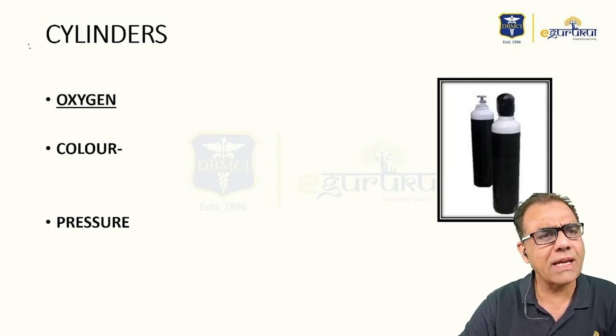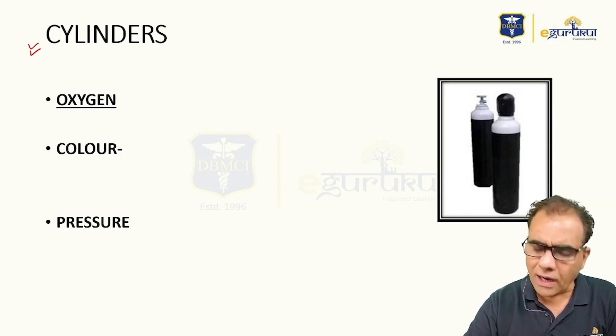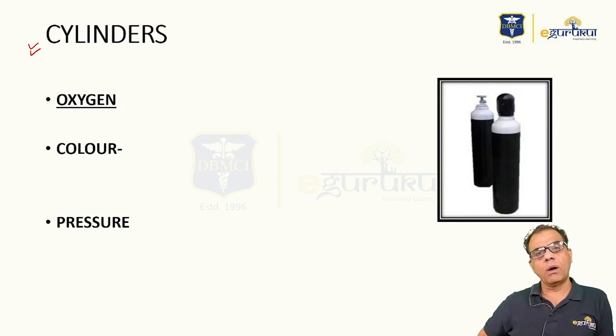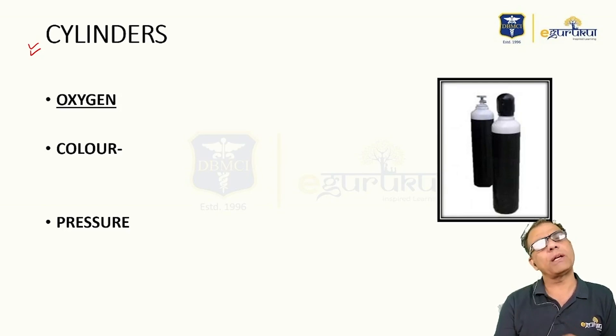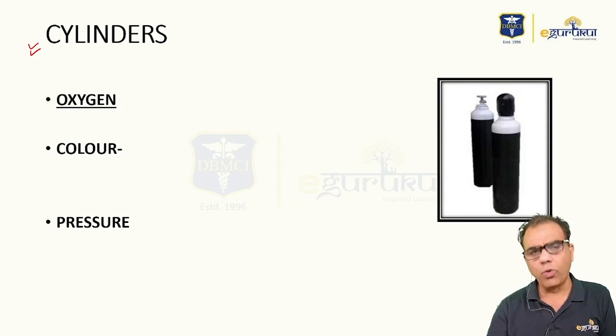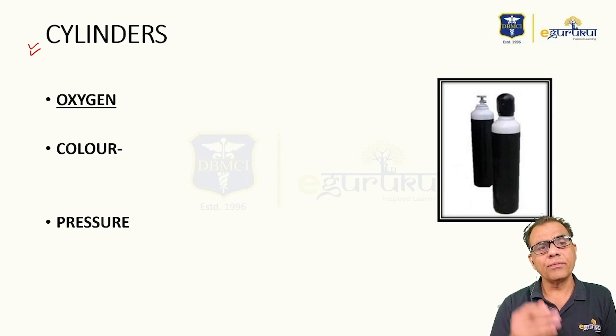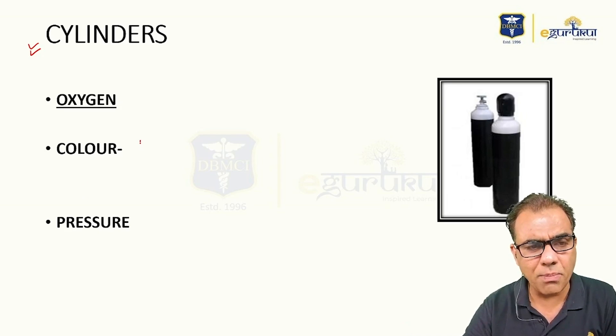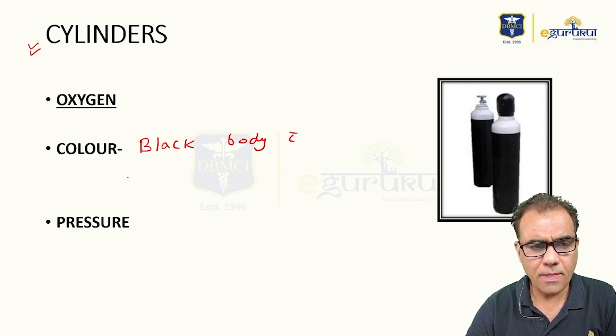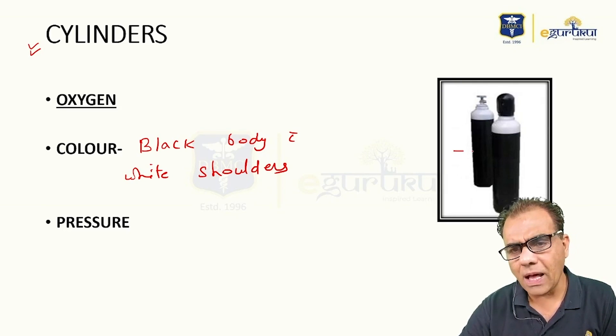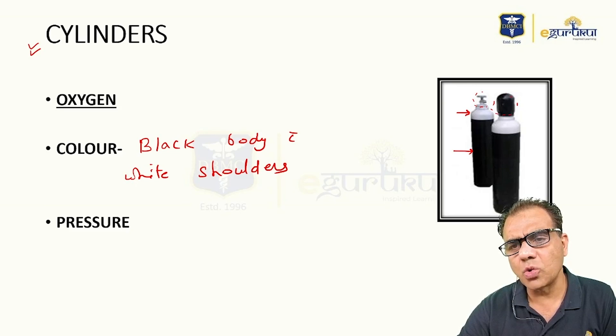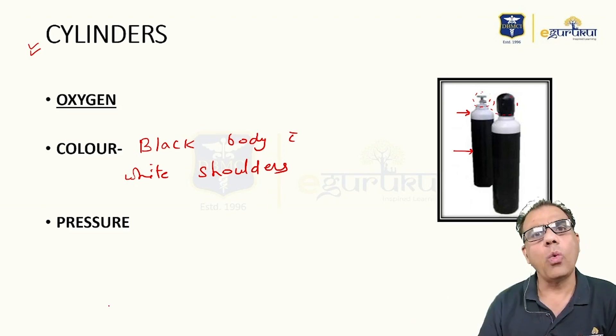Sources of gases can be cylinders. Regarding cylinders, two most important things you have to remember: one is the color of the cylinder and second is the pressure. Color is not only important from a questions point of view, it is also very important from a clinical point of view, because only if you know the color can you identify a cylinder. The color of the oxygen cylinder is black body with white shoulders — black body with white top — and this cover is just to protect the valve so that dust does not enter. So: black body with white shoulders.